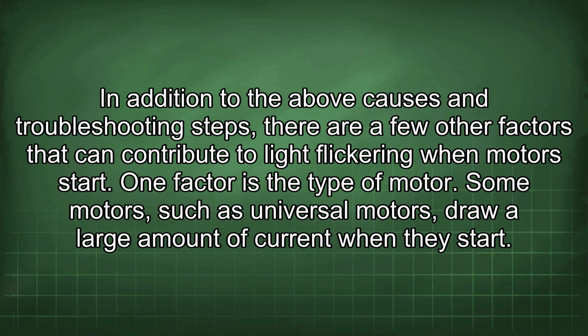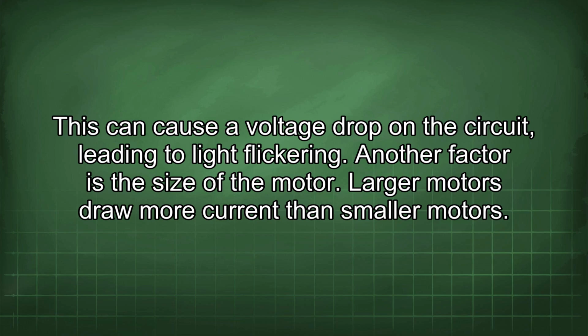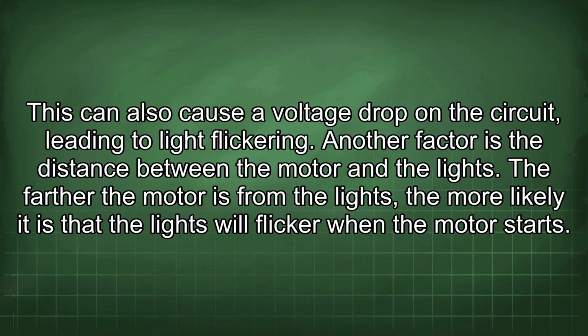In addition to the above causes and troubleshooting steps, there are a few other factors that can contribute to light flickering when motors start. One factor is the type of motor. Some motors, such as universal motors, draw a large amount of current when they start. This can cause a voltage drop on the circuit, leading to light flickering. Another factor is the size of the motor. Larger motors draw more current than smaller motors. This can also cause a voltage drop on the circuit, leading to light flickering.